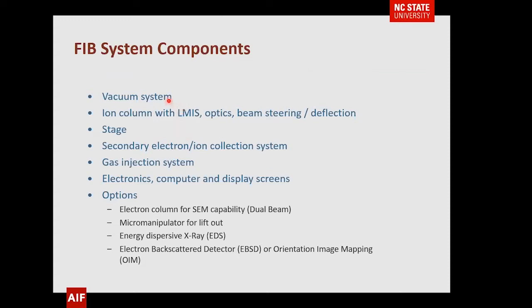What's in an FIB? We need a vacuum system — those ions don't go very far in air. We need an ion column with the source we'll discuss shortly. Optics, steering, deflection. We need a stage to move the sample. Something to collect the secondary electrons or ions. The gas injection systems are used for deposition and etch. Of course we need a computer. Most FIBs sold now have an SEM added, which makes the instrument much more capable. There's also an instrument called a micromanipulator to lift out samples, and you may have EDS and EBSD capabilities as well.